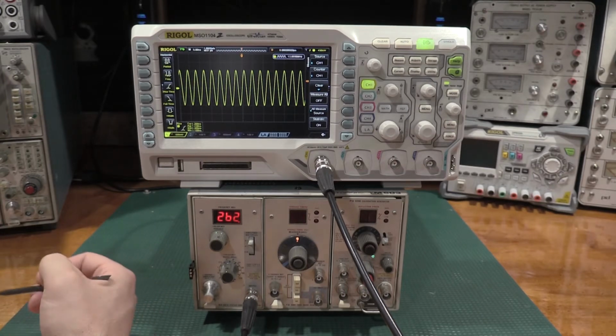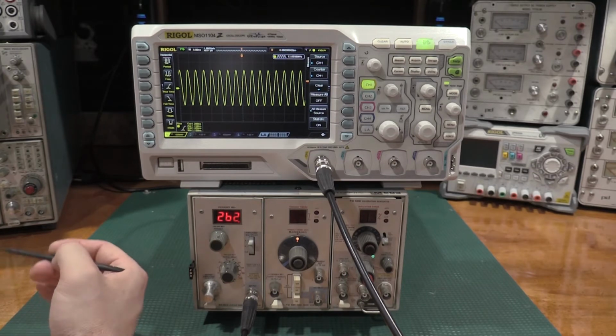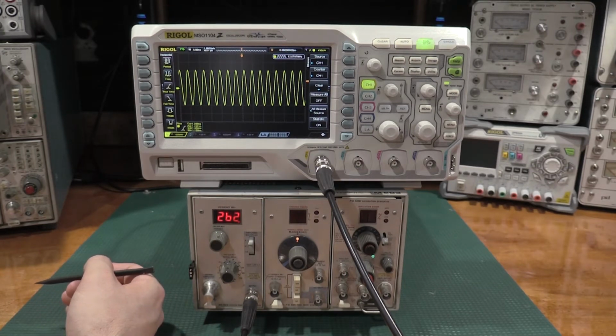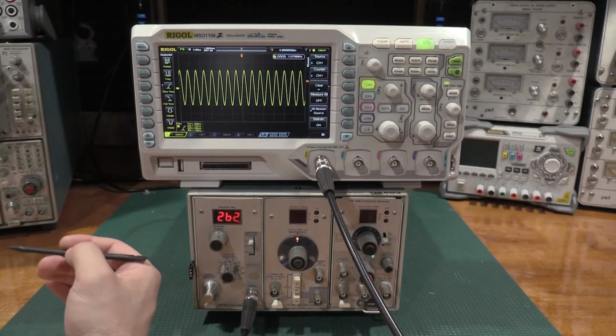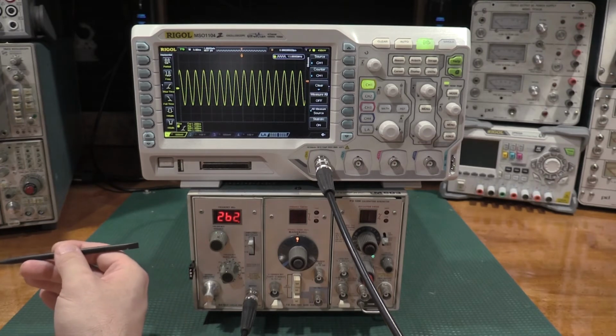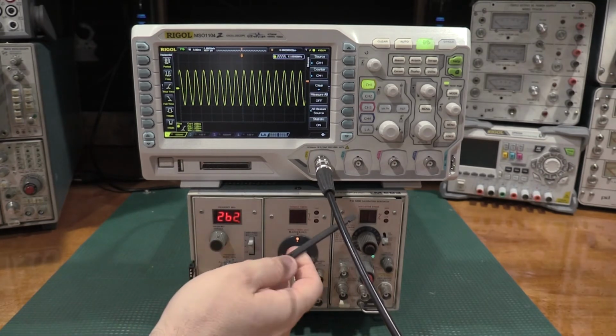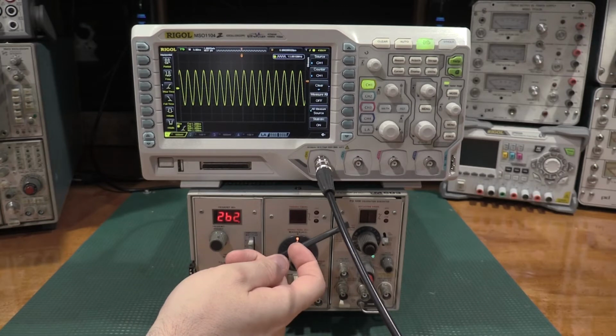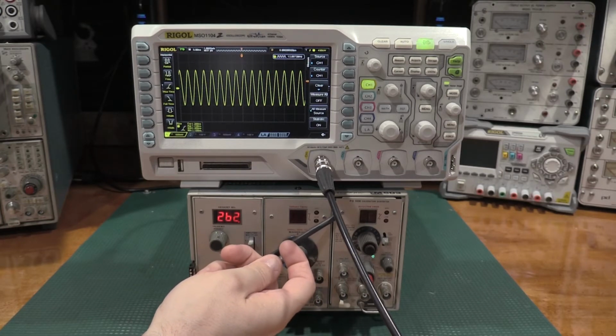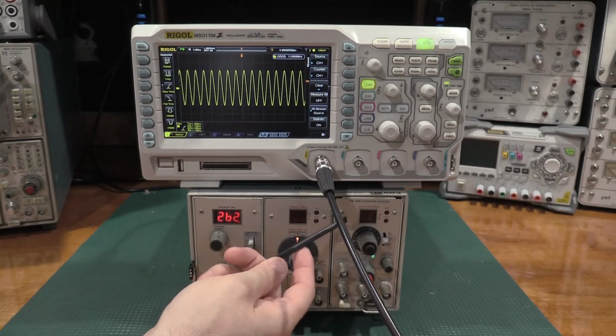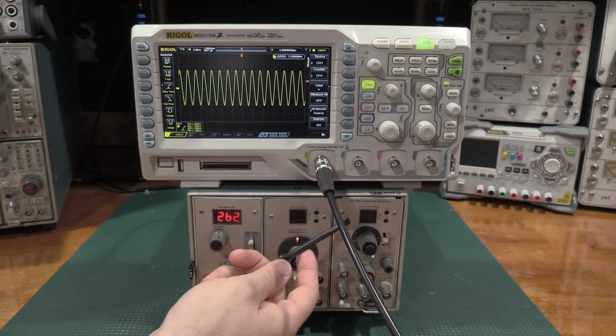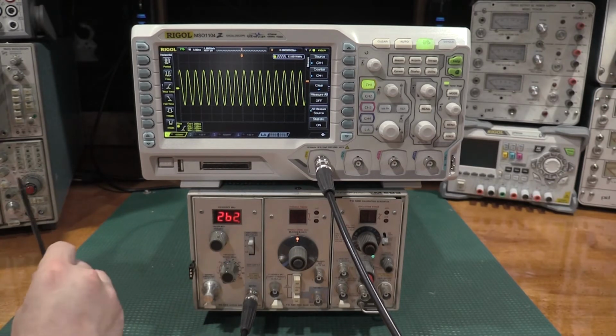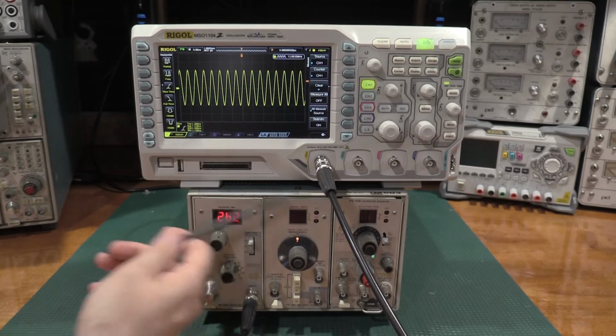You wouldn't be able to do the high frequency compensation because the arbitrary waveform generator may not be fast enough, and depending on the specifications of the arbitrary waveform generator, you may not be able to replace the PG506 with that one. The PG506 is a pretty accurate plugin, so you'd need to look at the overall accuracy of the ARB and make sure it would match the accuracy or better of the 506.